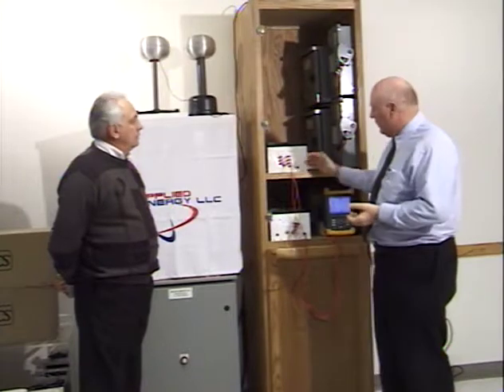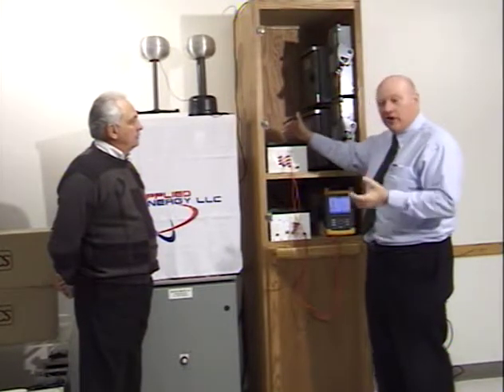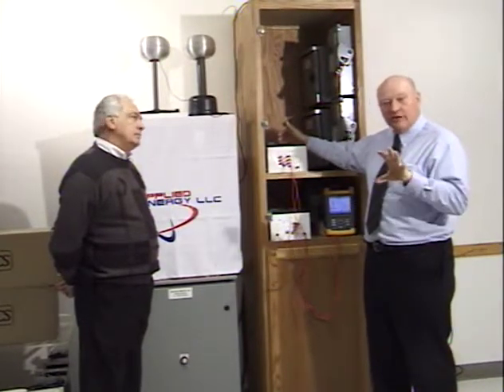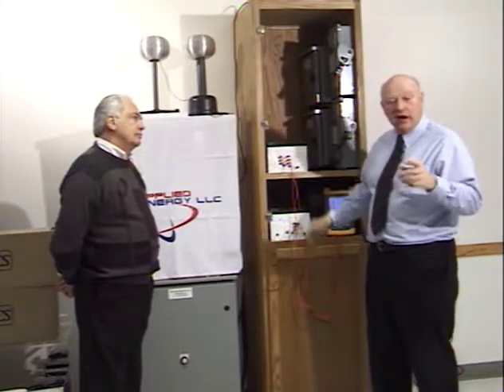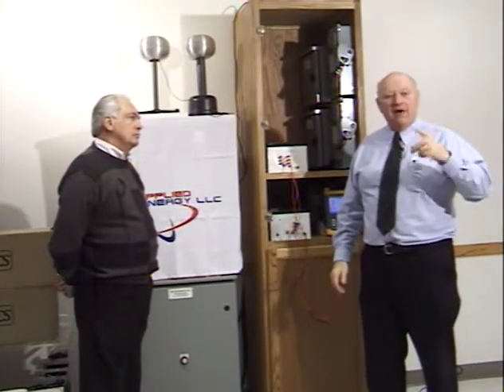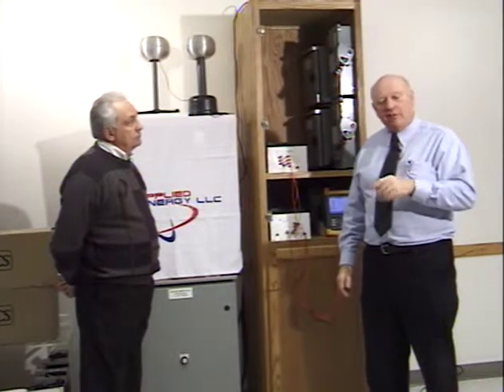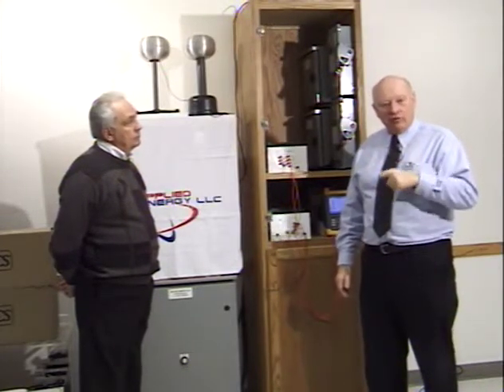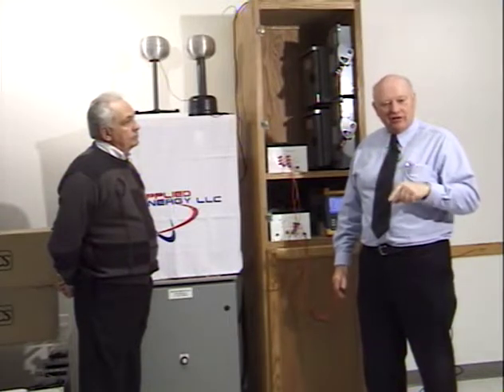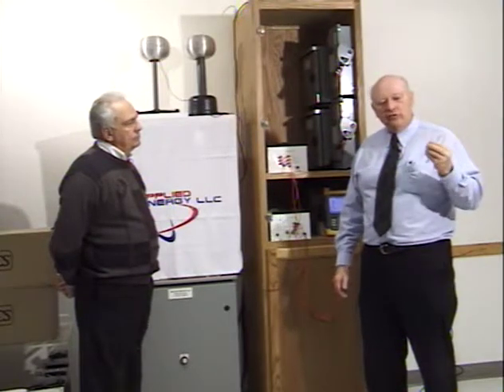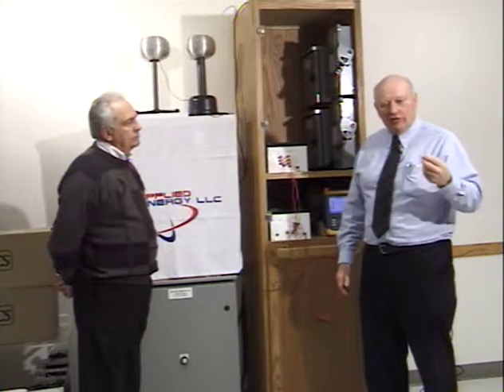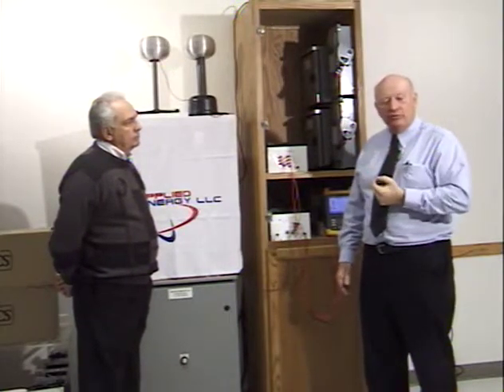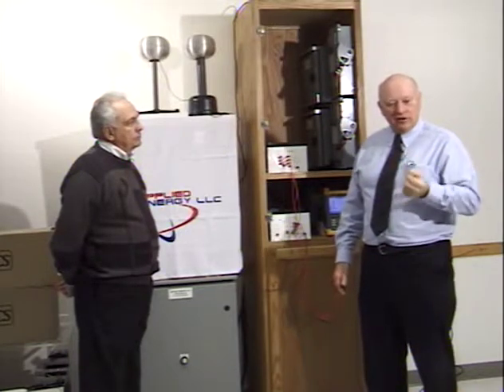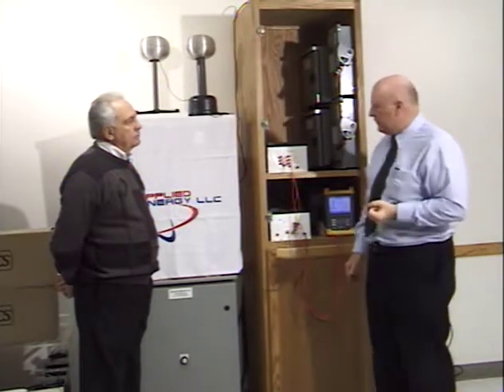And what they do with the motor, the 3rd harmonic we talked about earlier will try to make a motor stand still. 5th harmonic will try to make it run backwards 5 times faster than it's running forward. 7th harmonic will not only try to make it run forwards 7 times faster than it's running, but it'll try to induce or cause current through the motor shaft. The only way that current can have a path to flow would be through the bearings, causes a little sparking and shortens the life of the motor bearings.